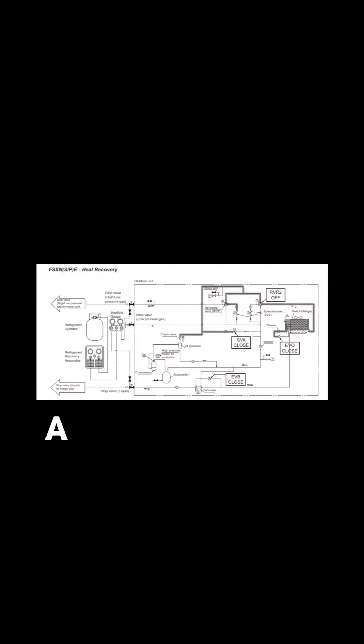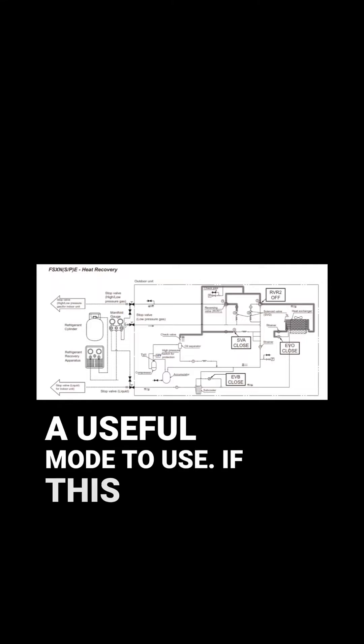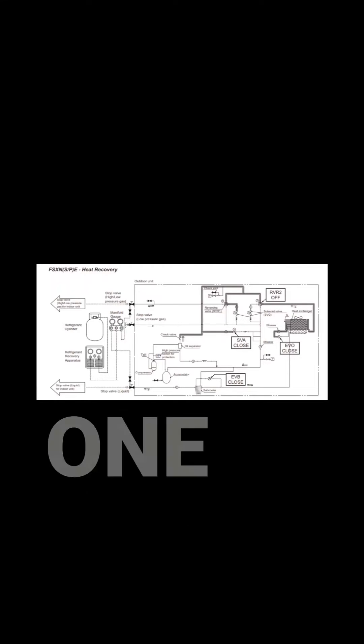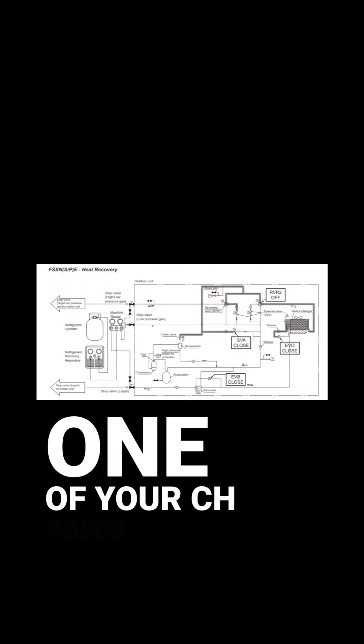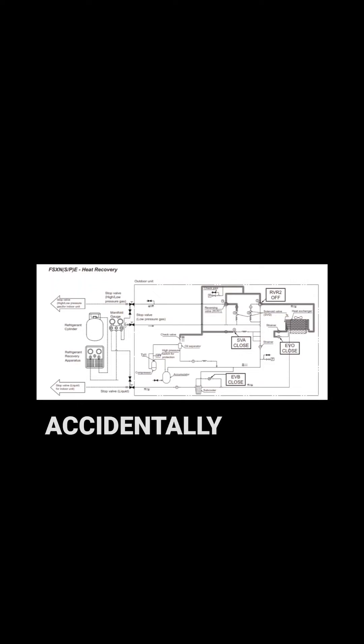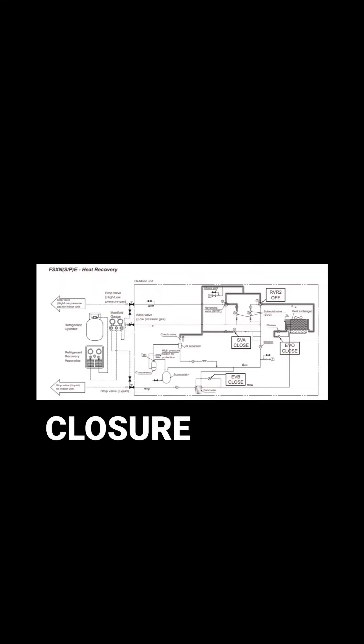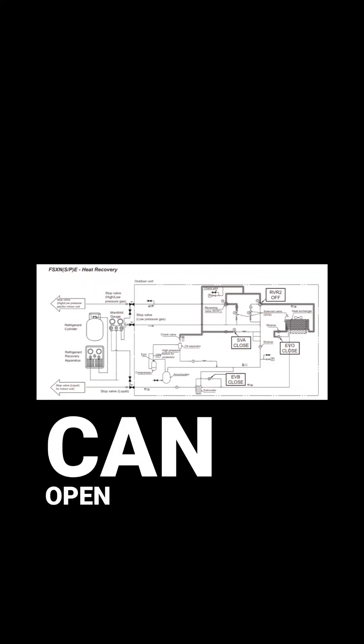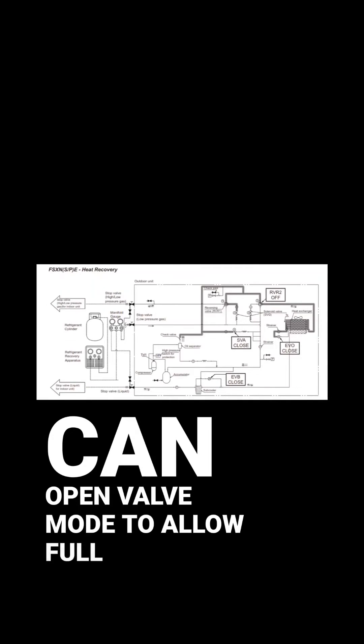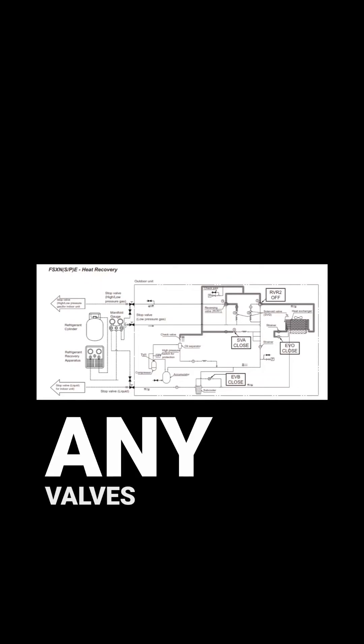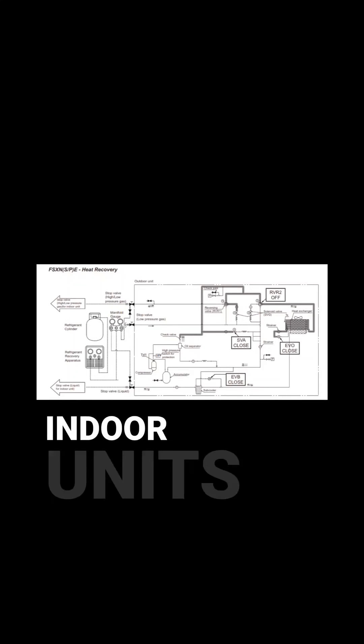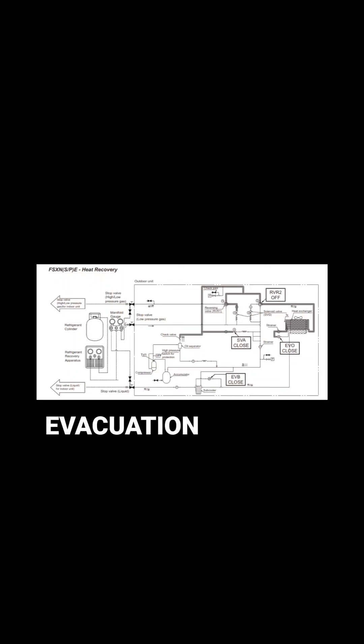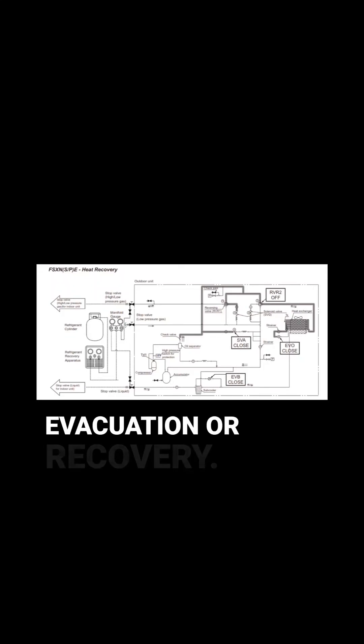It's also a useful mode to use if this is a new installation and you believe one of your CH boxes or indoor units has been powered up accidentally, resulting in the closure of one of the valves. You can open valve mode to allow full access to all the pipe-side stuff, opening up any valves in the CH boxes and indoor units, allowing you to carry out a full pressure test, evacuation or recovery.